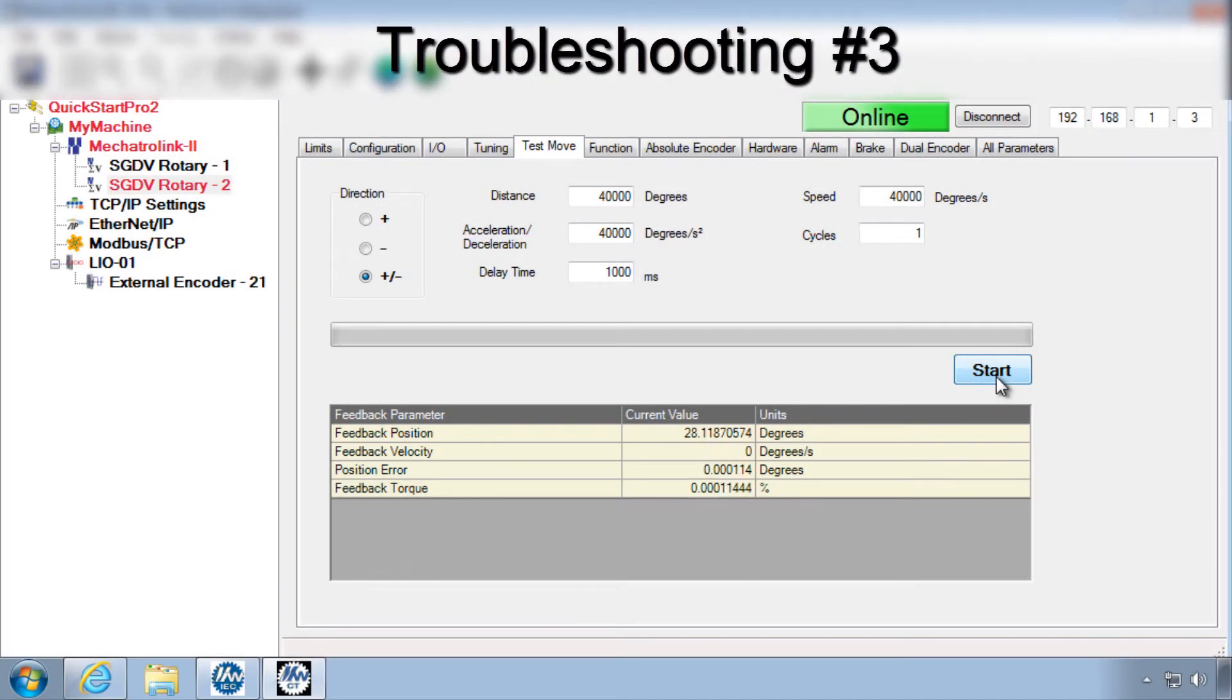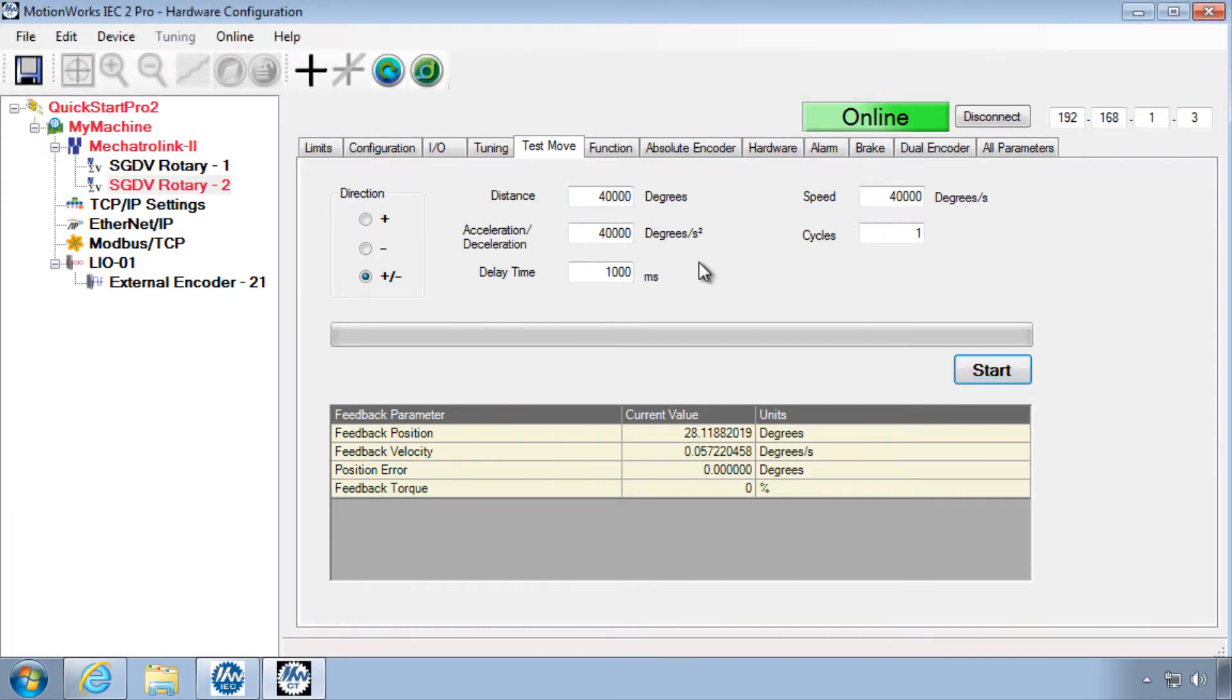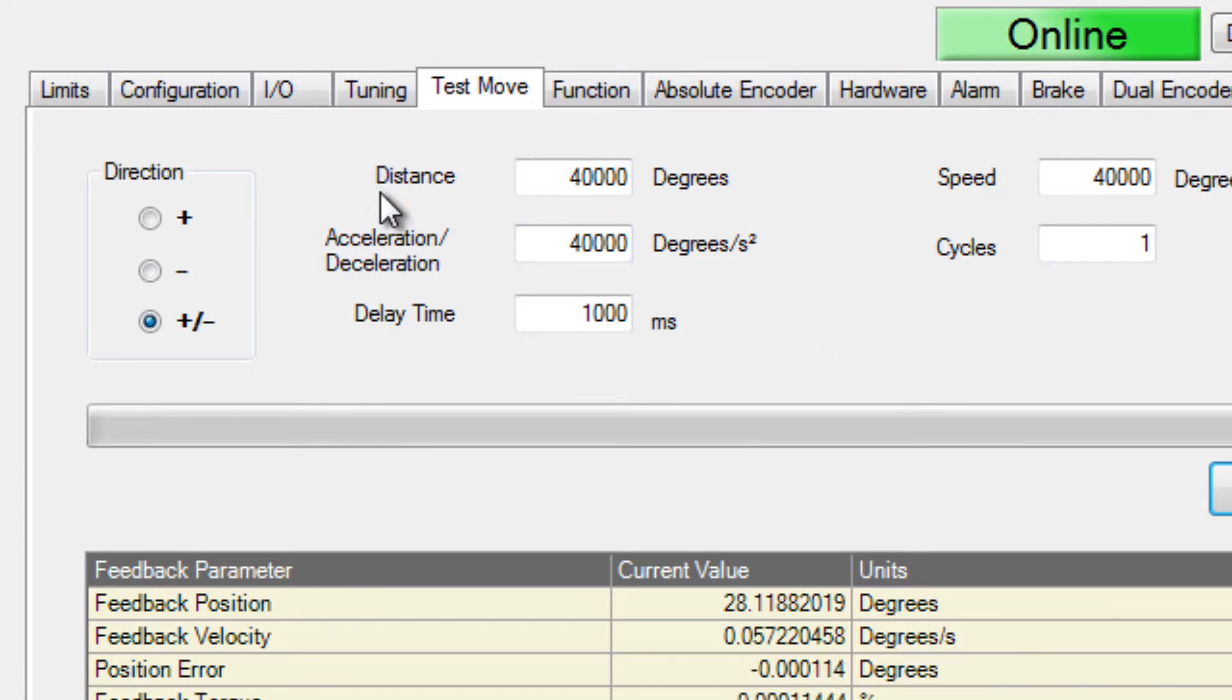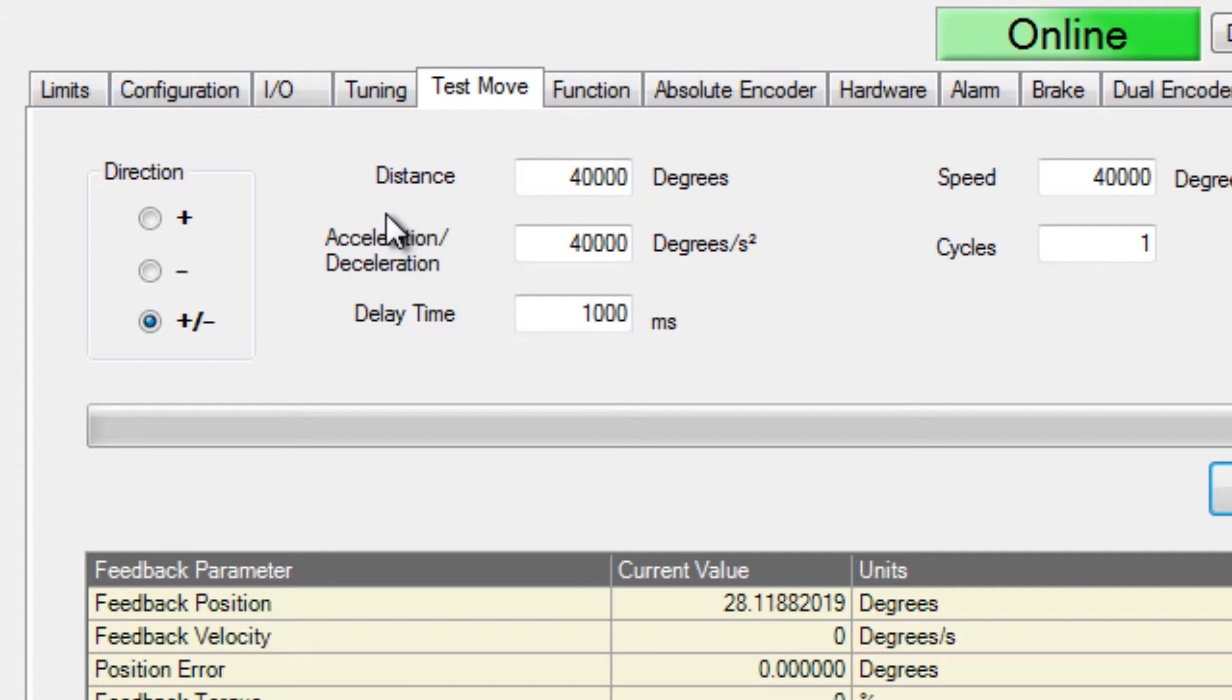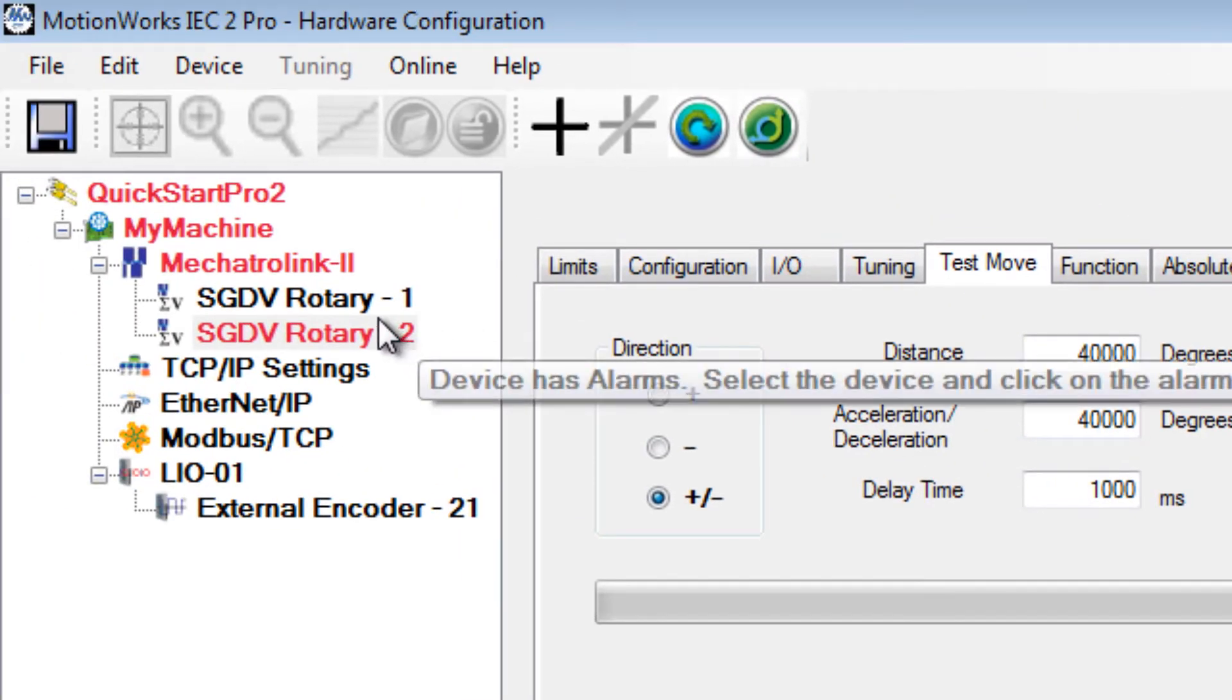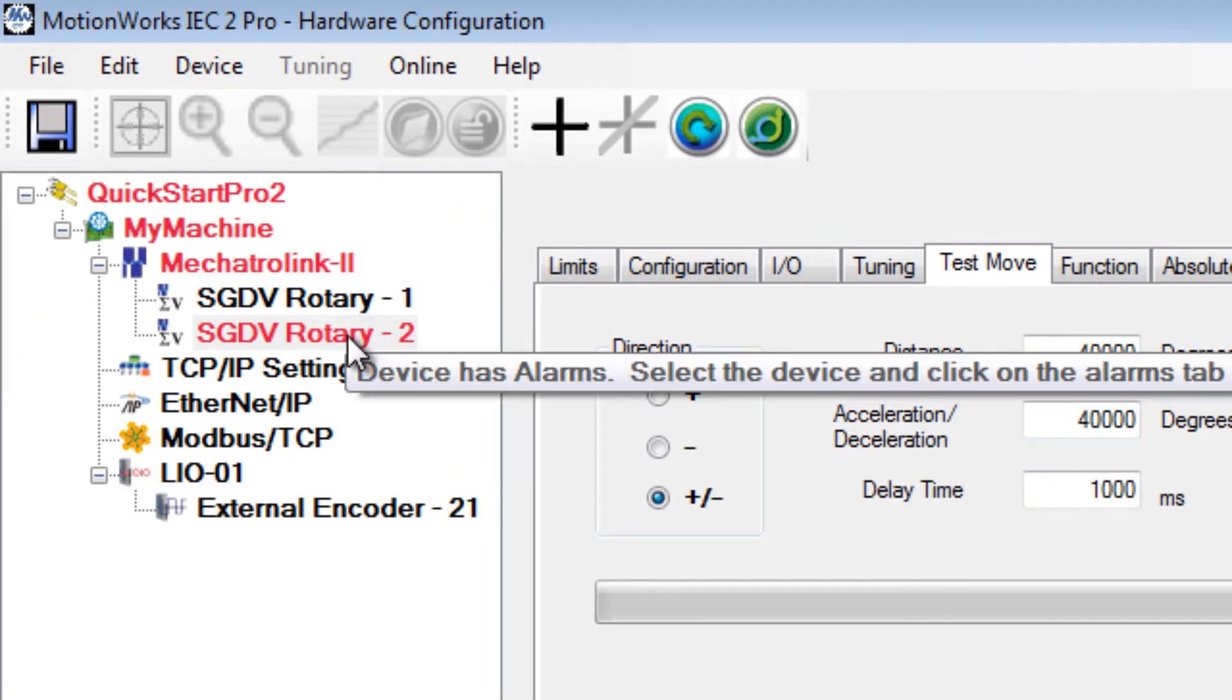If an alarm is generated during the test move, the data you've entered may be out of range or the units configured incorrectly. Over speed or position error alarms often are the indicators for this problem, and you can see that the alarm axis has a red color.